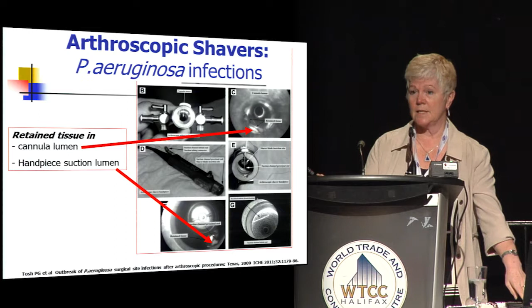So one of the things that FDA is on the warpath about, and that's my opinion, of course, they don't say they're on the warpath about anything, but they are really looking at the validation that's being done by manufacturers. Because if you're following the manufacturer's instructions for use and you still have residual pieces of tissue in your handpiece, what gives? That shouldn't happen if they truly validated their method with the right test materials.